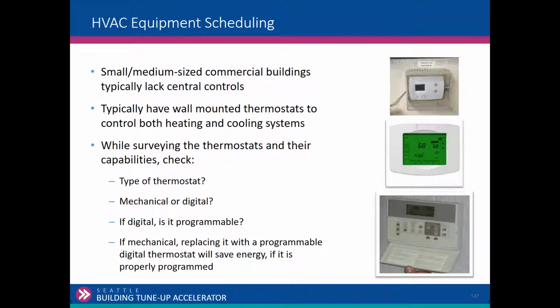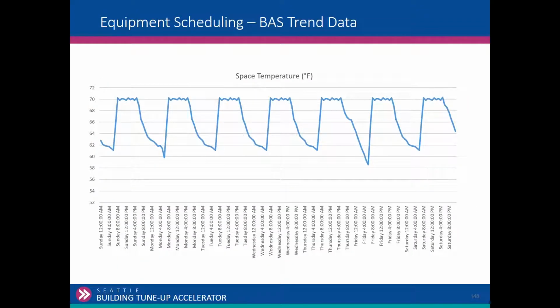Okay, so if you don't have a BAS system, equipment scheduling is probably pretty simple, right? It's a programmable thermostat or a time clock, right? So pretty easy to check to see if the thermostat time setting is correct. Has anybody seen a thermostat with the wrong time setting, right? Daylight savings time, it's on a weekend, whatever's going on. Pretty easy. So, is it set to the right time? Does the schedule meet occupancy? Pretty straightforward stuff. We could trend it too.